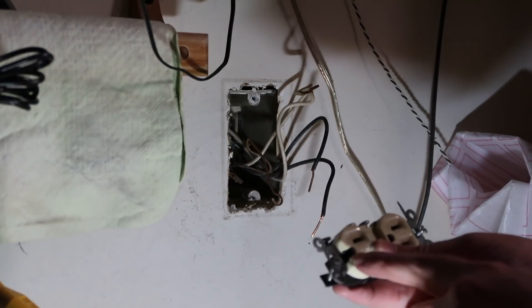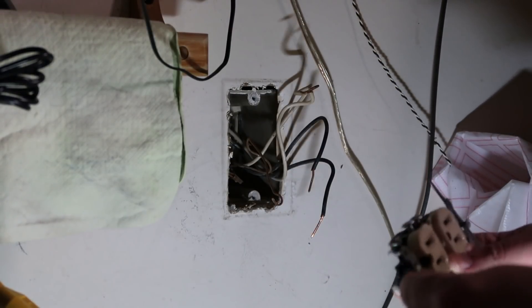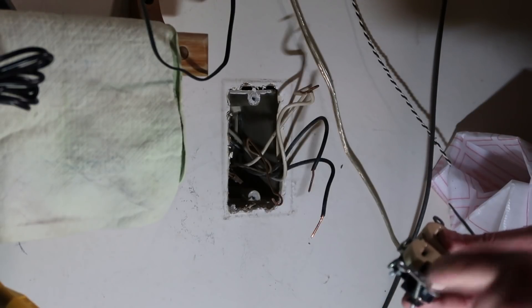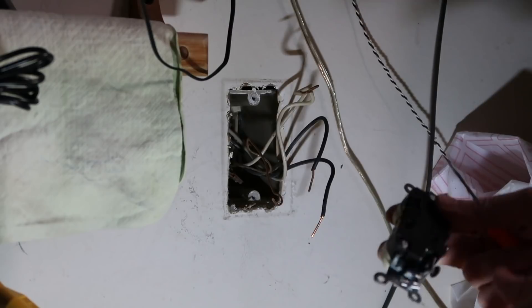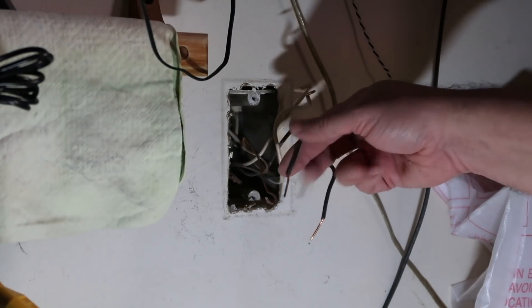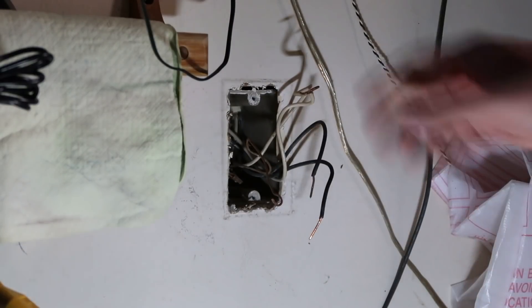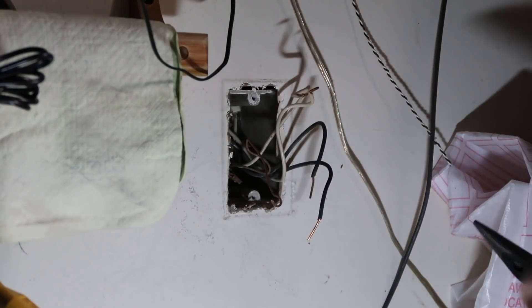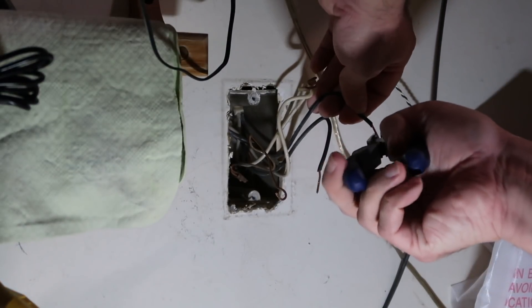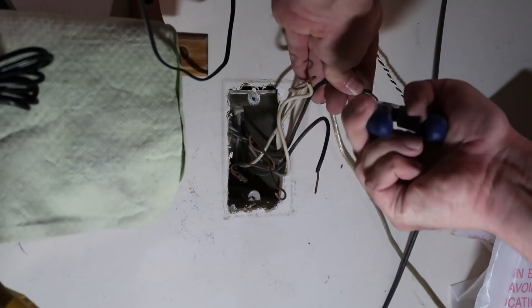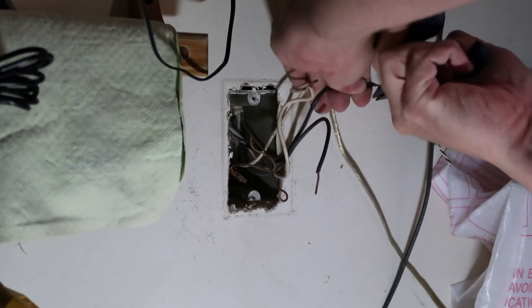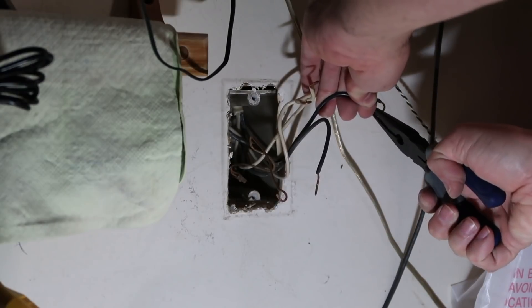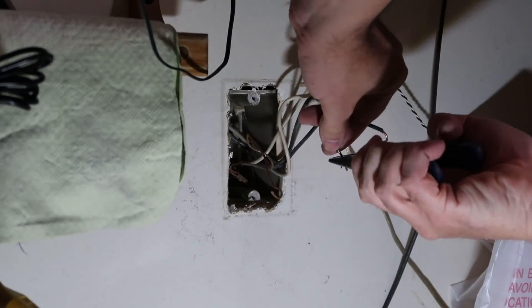Now we have the outlet out. There you go, you can see it's broken at the bottom here, it doesn't have this little bottom part. So essentially the ground wire could actually touch the actual ground of the outlet. So since these black wires, which are the hot wires, and the white wires are the neutral wires.